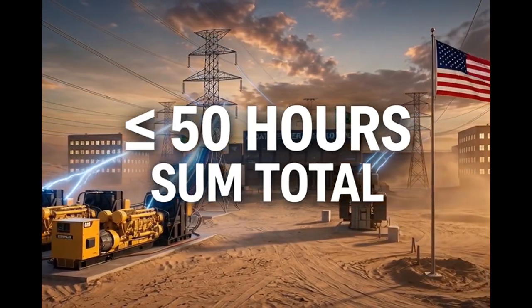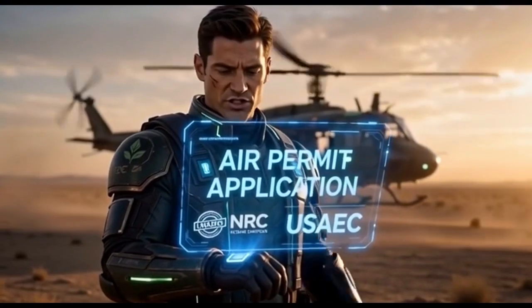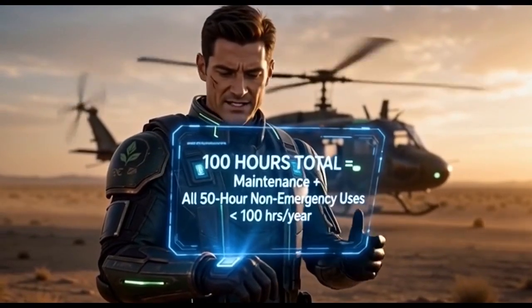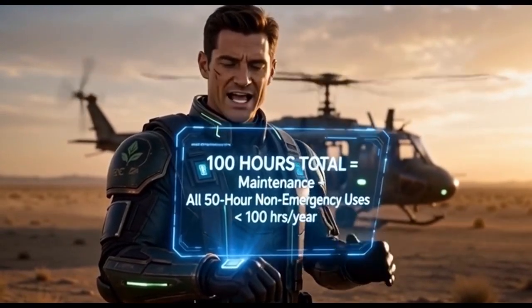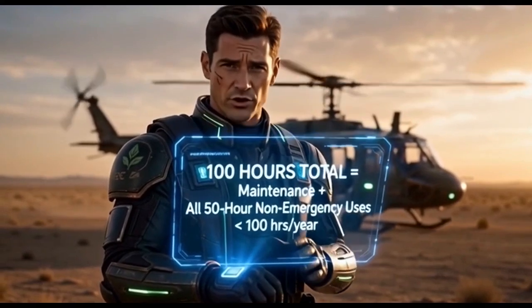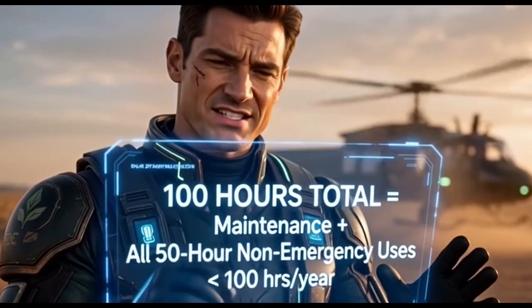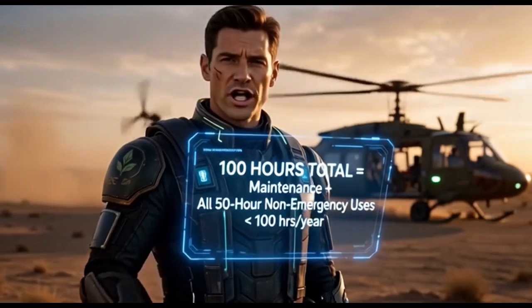Log every hour. Team, the sum total of every hour your engine runs for maintenance, load bank testing, engine maintenance, plus all the allowed non-emergency uses has to stay under 100 hours per engine per calendar year. The 50-hour non-emergency stuff is inside that 100-hour cap. Go over it and you lose emergency engine status. Track it tight. Here's the quick reference, team.